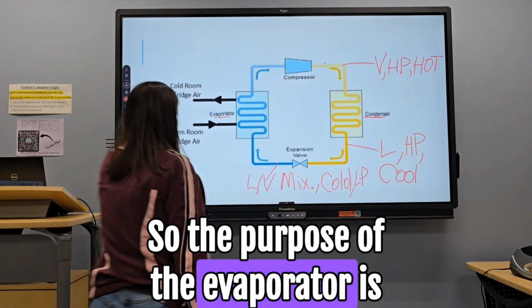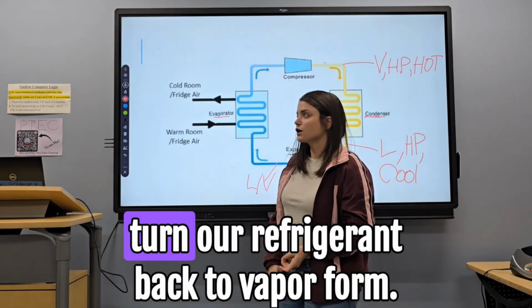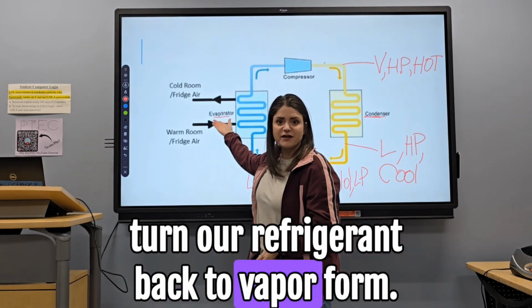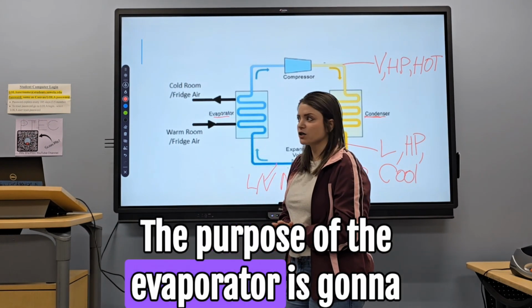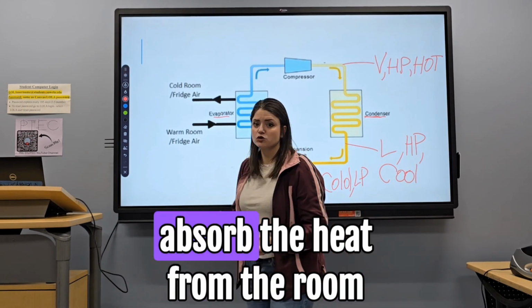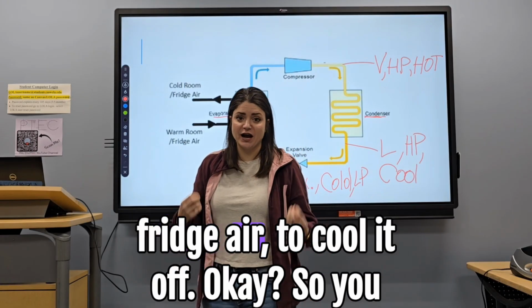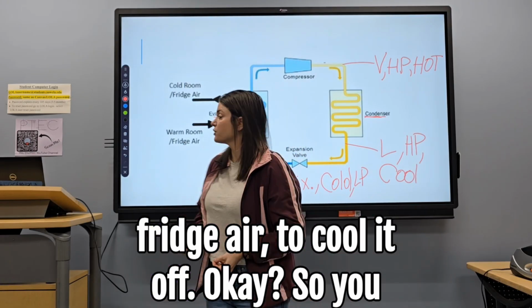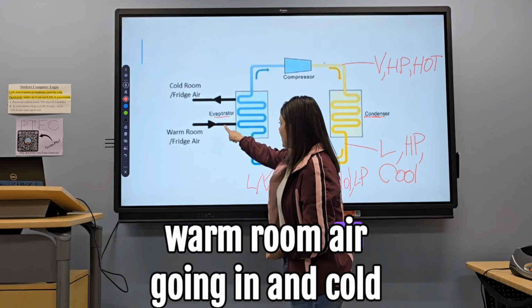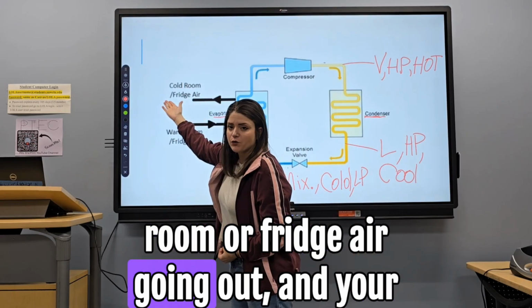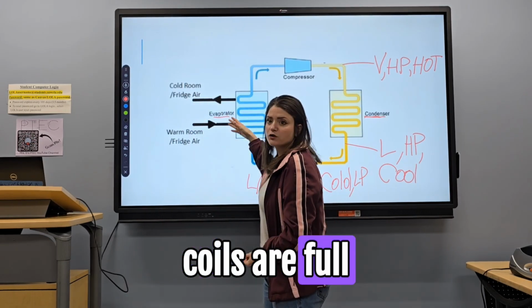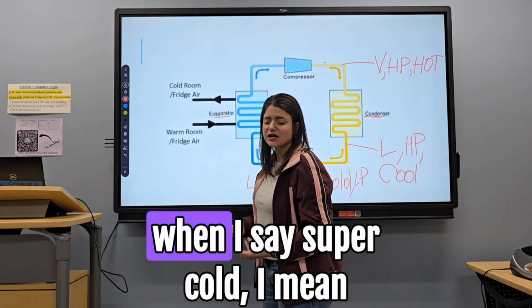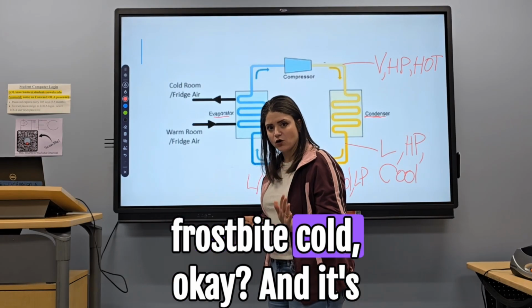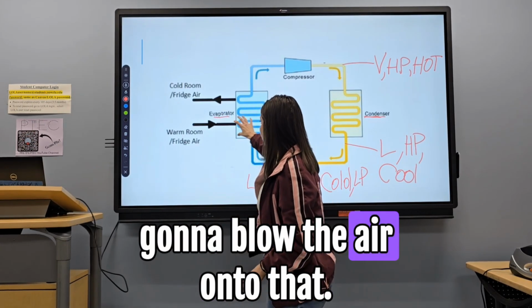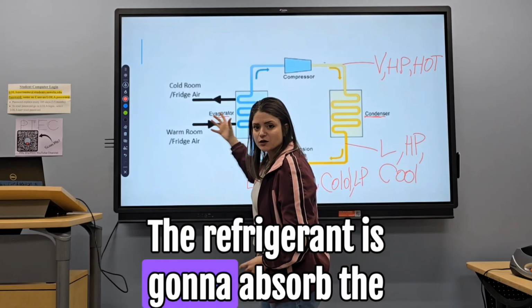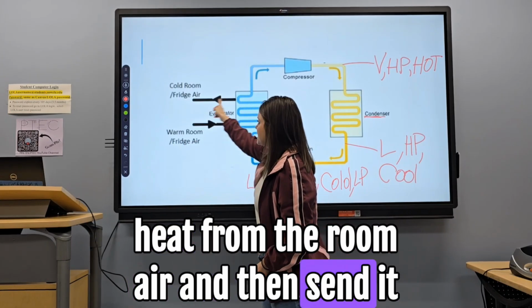So the purpose of the evaporator is not to turn our refrigerant back to vapor form. The purpose of the evaporator is for the refrigerant to absorb the heat from the room or fridge air to cool it off, okay? So you have warm room air going in and cold room or fridge air coming out. Your coils are full of super cold refrigerant. And when I say super cold, I mean frostbite cold, okay? And it's going to blow the air onto that. The refrigerant is going to absorb the heat from the room air and then send it back out cold.